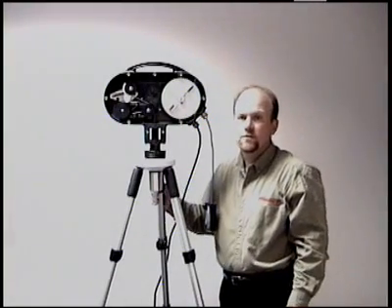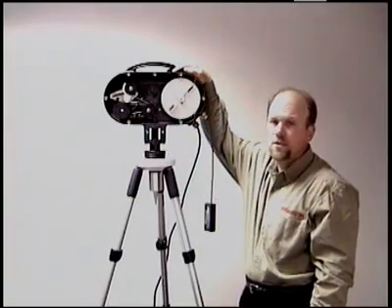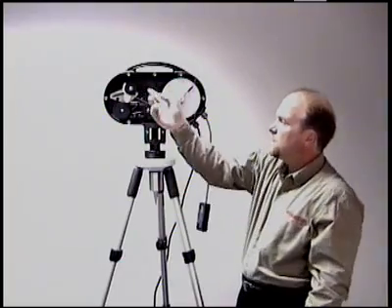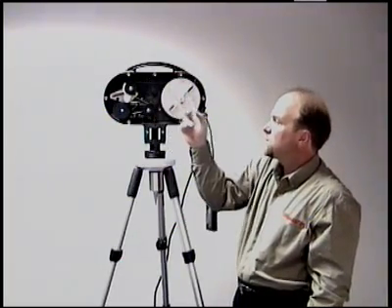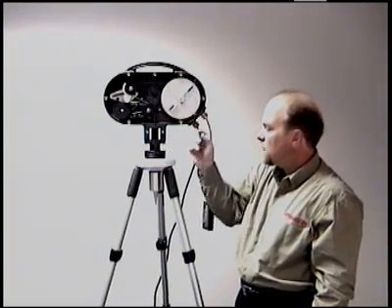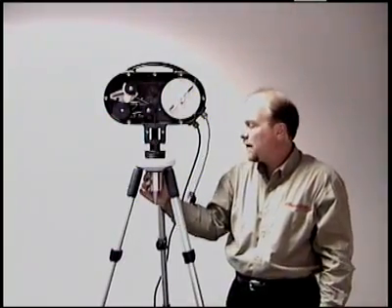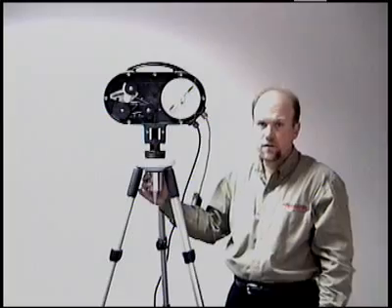Here's how SmartBOB2 works. An SBR2 remote sensor is mounted on top of the vessel. A motor releases stainless steel cable from the supply pulley, which causes a weighted sensor probe to quickly drop from the top of the vessel to the surface of the material.